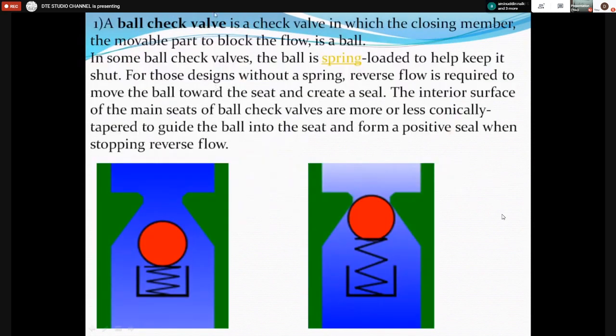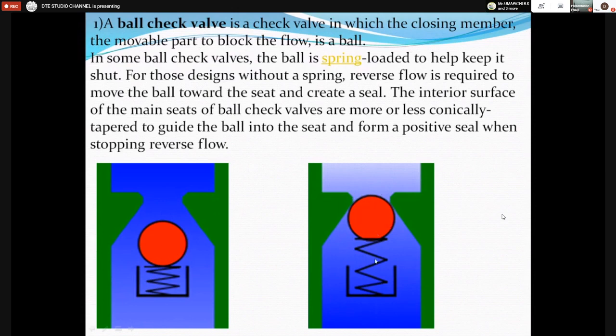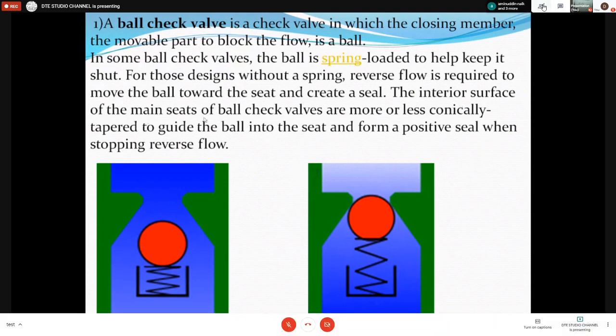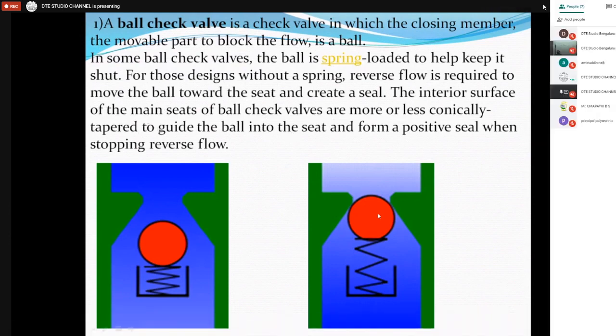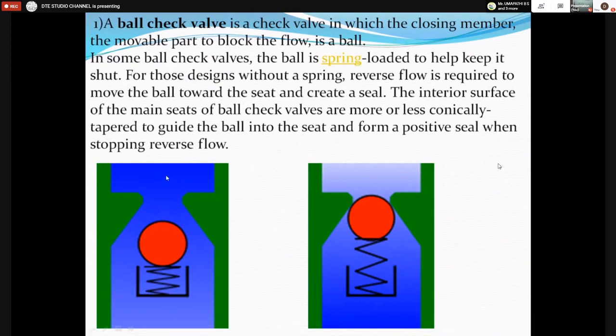The first type is a ball check valve. A ball check valve is a check valve in which the closing member — the movable part to block the flow — is a ball. Initially the ball closes the inlet port by means of spring force. The interior surface of ball check valve seats is more or less conically tapered to guide the ball into the seat. It is also known as a check valve or non-return valve because it allows flow of fluid only in one direction; in the reverse direction the ball automatically closes the port.